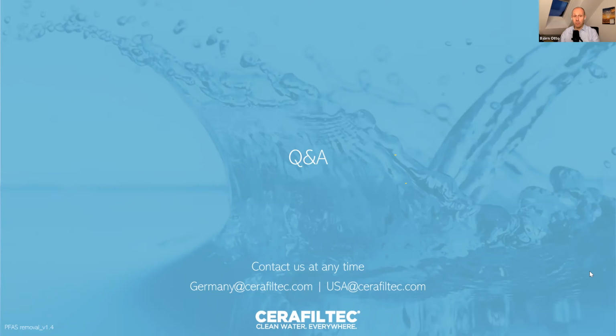What happens if the membrane breaks? How do you identify this? So we have integrity tests, we have leakage tests, we have all kinds of bubble tests to show if there's an issue. But the reality is that unless it's a ceramic, right, it doesn't like to be dropped on the ground. So usually ceramic should not break.